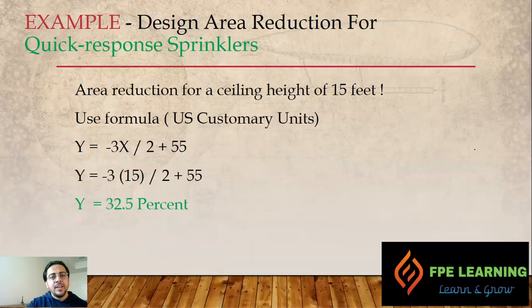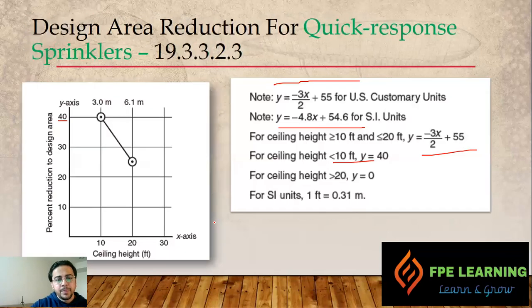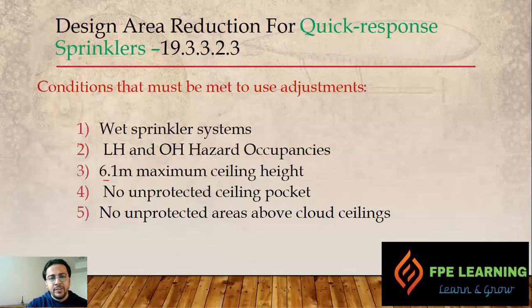Let's apply the formula for quick response sprinklers. If our ceiling height is 15 feet, we use the US customary formula: reduction = −3(15)/2 + 55 = −22.5 + 55 = 32.5 percent. So for a 15-foot ceiling with quick response sprinklers, we can reduce our design area by 32.5 percent. This is how we read the graph and apply the knowledge to select the best fire pump sizing while reducing cost.